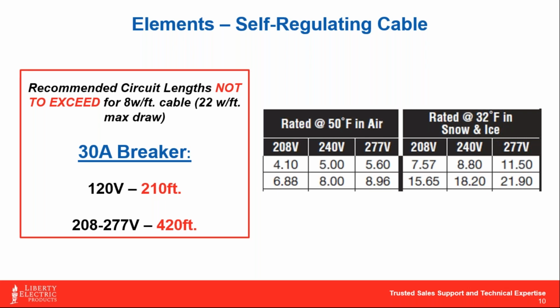Here's another slide that really depicts a bit more of what we're talking about as far as sizing the breakers. And again, this is the most complicated part about this particular cable, being that we can't load past 80% rated duty of that breaker. When we look at an 8 watt a foot cable for this example, it actually has the ability to draw 22 watts a foot. So when we're looking to put that on a breaker, if I'm using 120 volt as my voltage, I can only go up to about 210 feet of 8 watt a foot heat cable on that circuit. And if I'm somewhere between the 208 and 277, I'm maxing out around 420 feet.